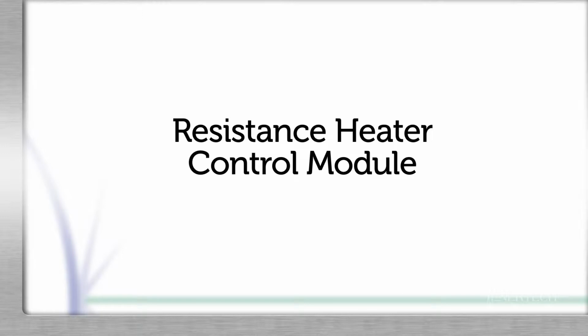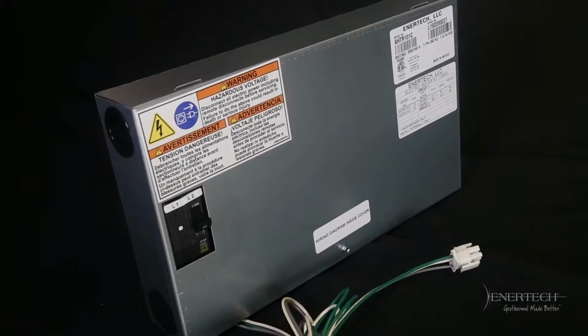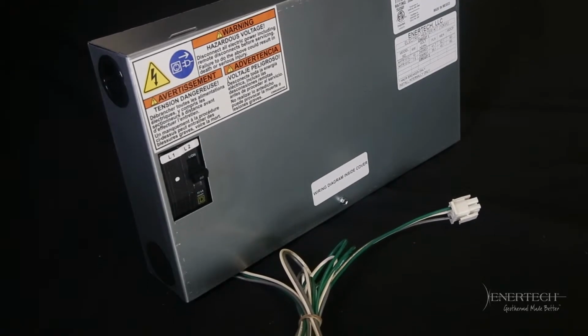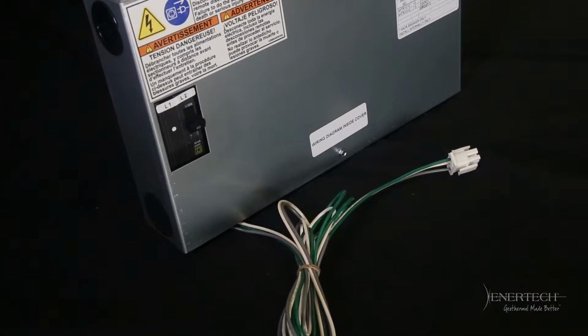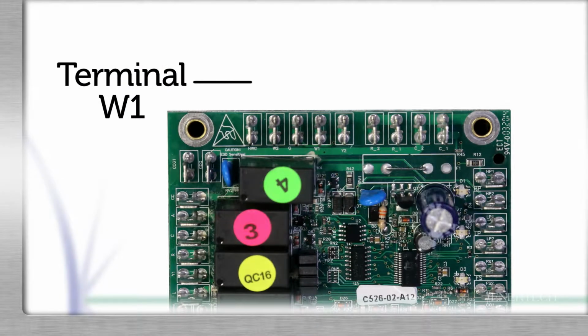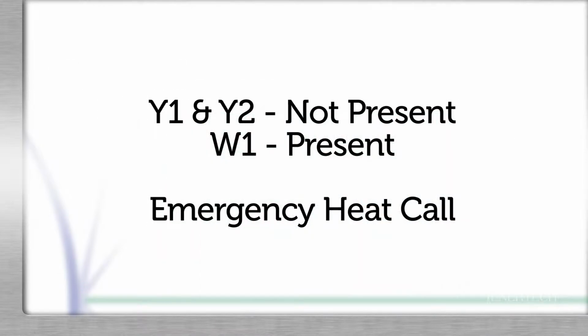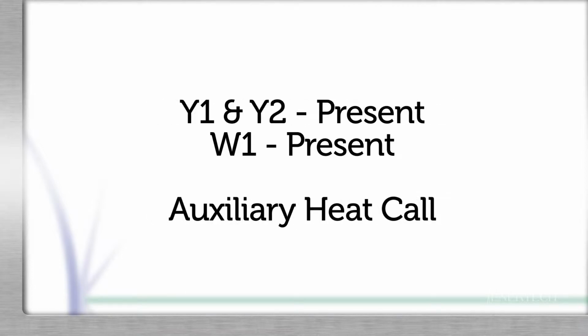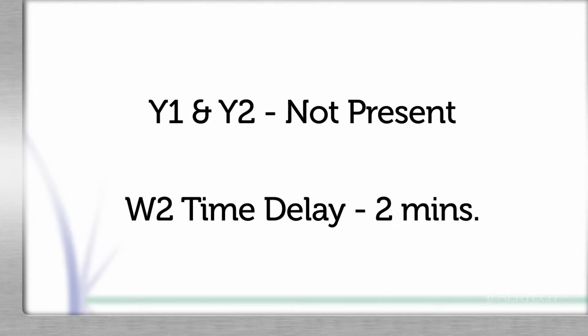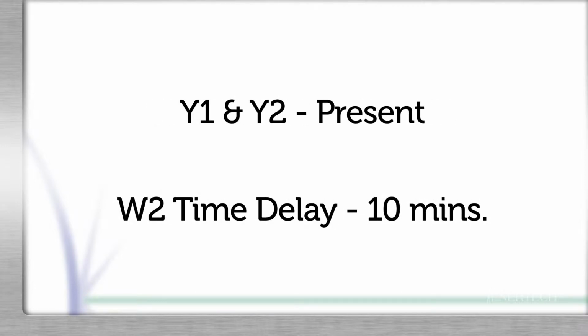The resistance heat control module contains the appropriate high voltage control relays. Low voltage control signals from the lockout board energize the relays in the resistance heat module to engage backup resistance heat when necessary. The lockout board offers a pass-through W1 signal, first stage resistance heat, and a relay output with a time delay for the W2 signal, second stage resistance heat. If Y1 and Y2 are not present and W1 is present, the board recognizes this as an emergency heat call. If the Y1 and Y2 are present with the W1, it recognizes the call as an auxiliary heat call. When the Y1 and Y2 are not present, the time delay for the W2 relay is 2 minutes. When the Y1 and Y2 are present, the time delay for W2 is 10 minutes.